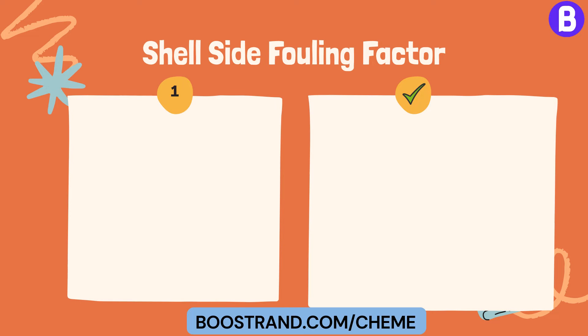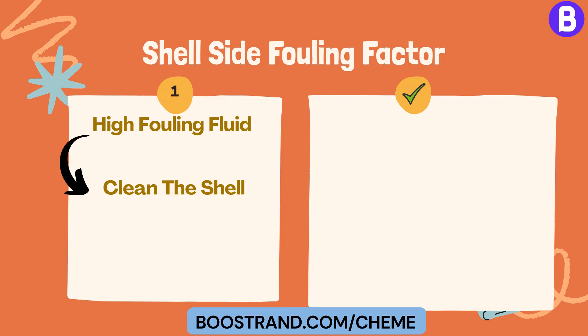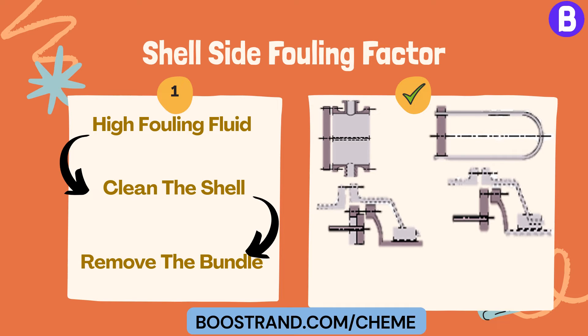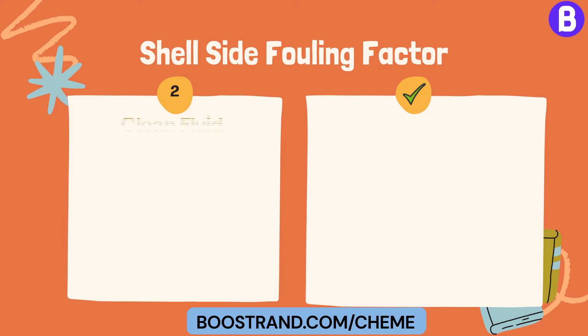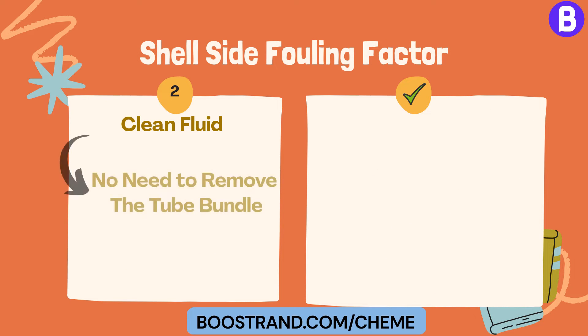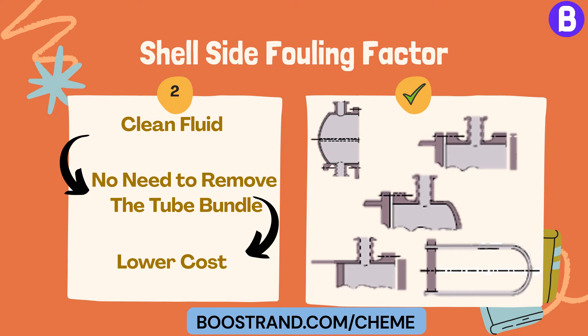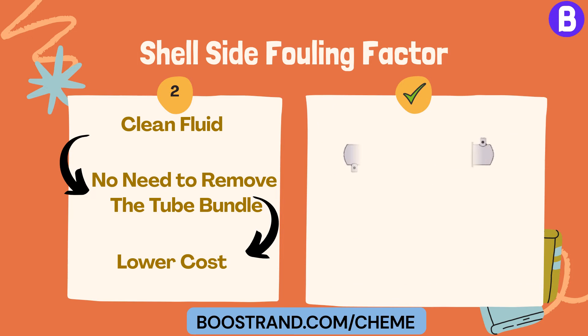If the shell side is serving a high fouling fluid, we will need to clean the shell, so the bundle should be removable. In this case, we should choose Type A for the front head and Type S, T, or U for the rear head. For a normal shell, the exchanger type shall be AES, AET, or AEU. If the fluid in the shell side is clean, we don't need to remove the tube bundle to clean the tubes from outside, resulting in smaller dimensions and lower cost. So we can use Type B for the front head and L, M, N, or U for the rear head — giving TEMA types BEM, BEN, BEL, or BEU.